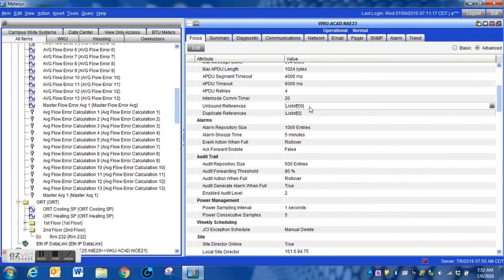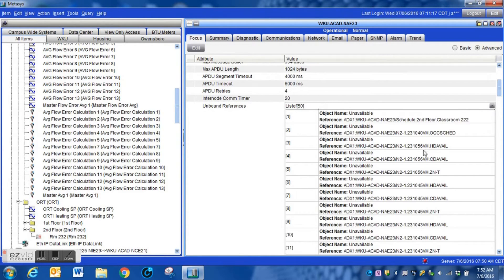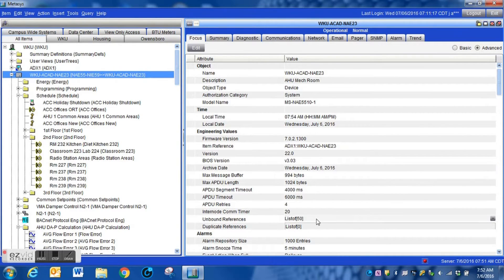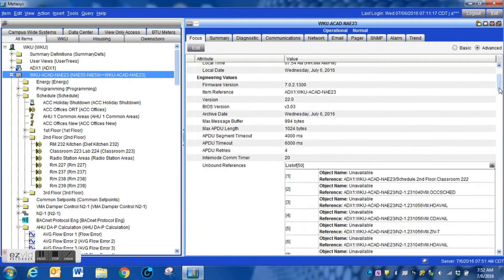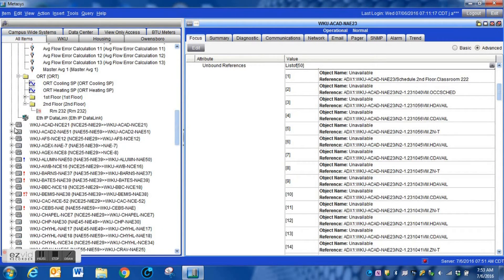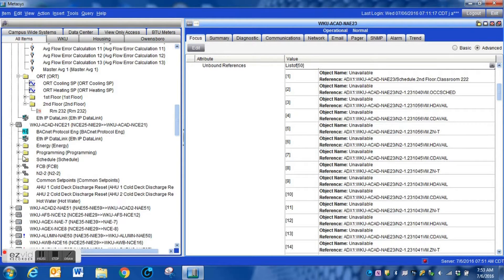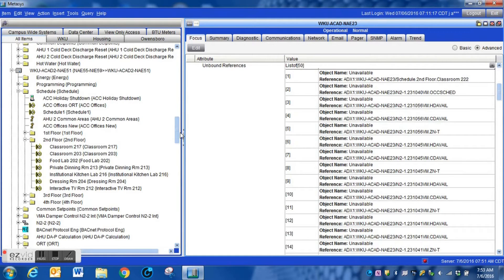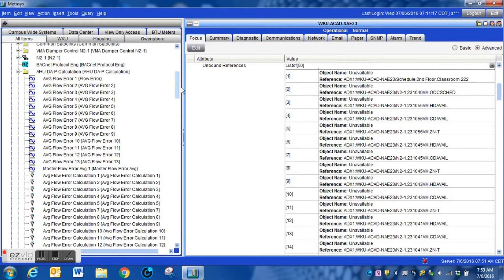That will reduce the number of unbound references within the system. I recommend that you dig through each of the logic blocks within your system until you can get that reference number down to zero. There are certainly many areas that could easily have unbound references, and these logic blocks can get quite large and complex. Going through all of them will help your system run much smoother and slow down resource usage inside your NAEs and NCEs.